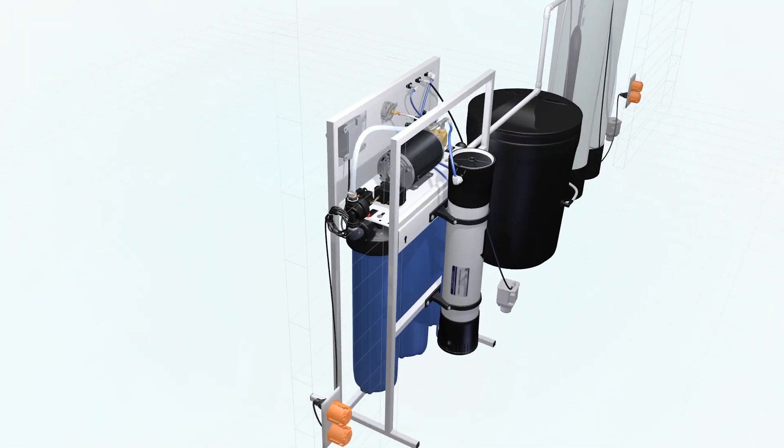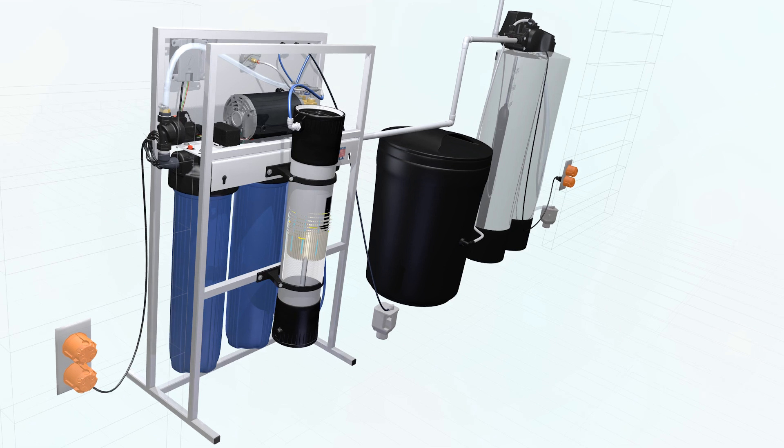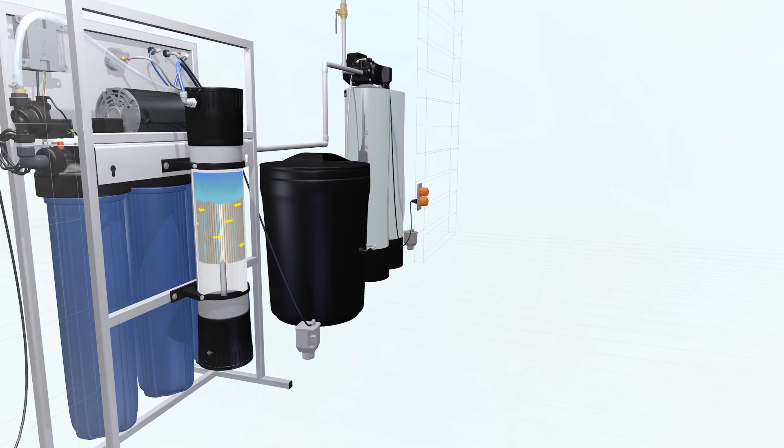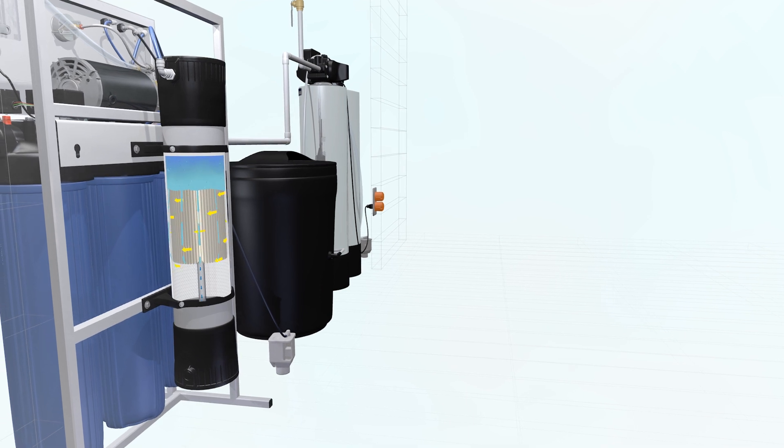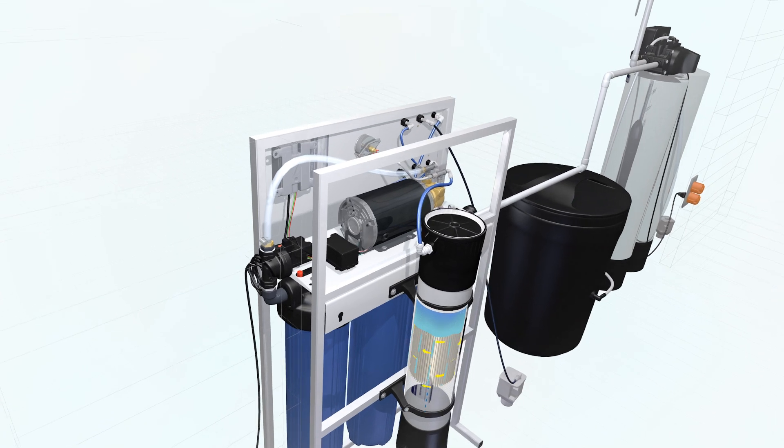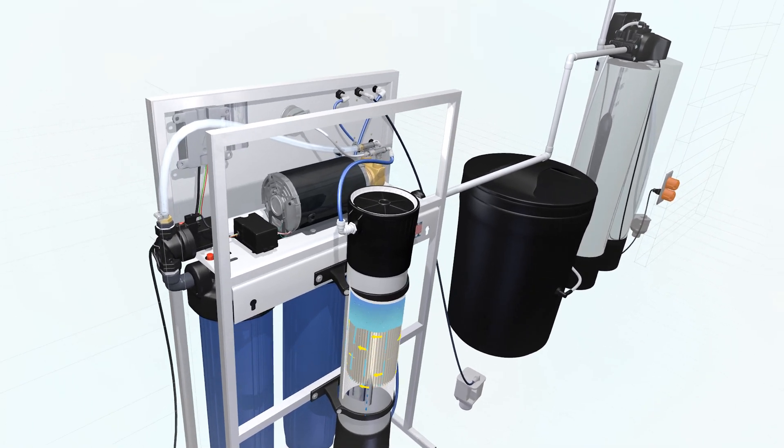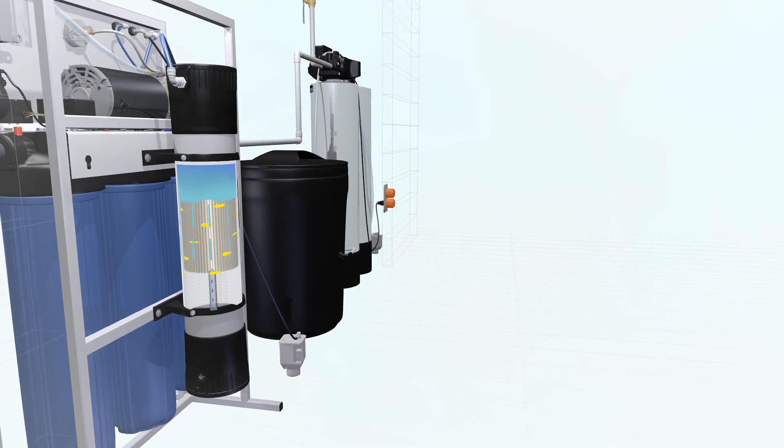The final stage is the reverse osmosis process. Water is forced under high pressure through the semi-permeable thin film composite membrane. The MRC series comes with a high-pressure booster pump to ensure maximum efficiency and water production. High and low pressure switches automatically monitor and protect the pump and motor.